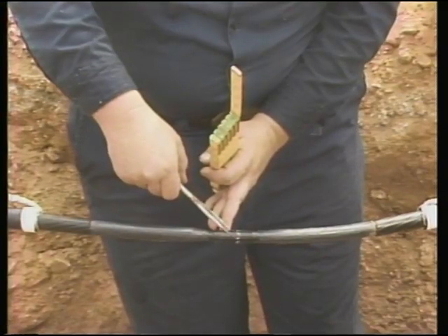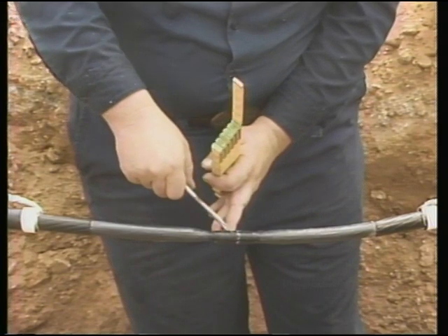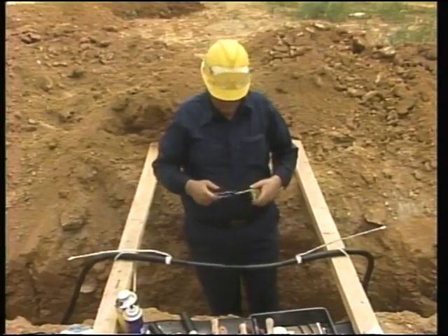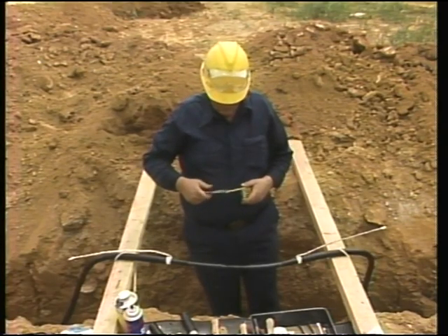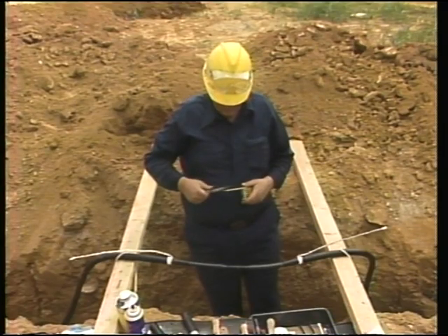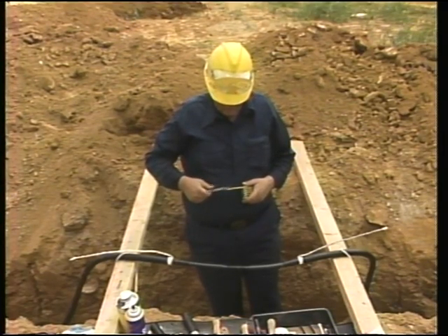Before applying it, the workman measures the connector diameter to calculate the insulation tape buildup. He'll then adjust his calipers to measure the insulation tape's final thickness. He can then spot check the cable as it's wrapped for the correct amount of insulation tape buildup.